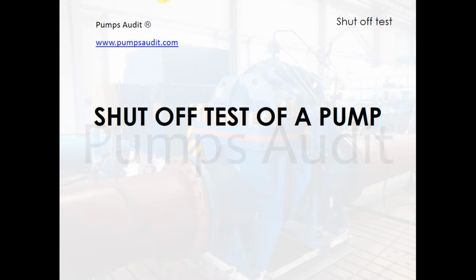Pipes have sediments, corroded, that cannot allow ultrasonic signal penetrate through pipe walls. And very often we are not sure whether measured parameters are correct. The shut-off test is one of the cross-validation methods which allows pump users to validate measured parameters.